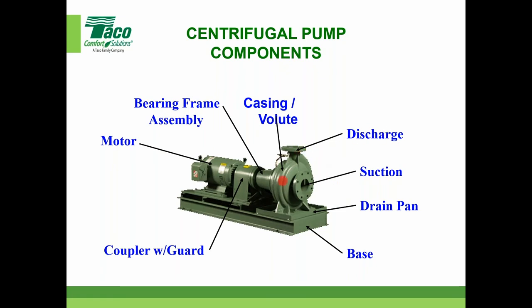Discharge, I think that makes sense. Casing, volute, wet end, they're all synonymous. Bearing frame, we're going to talk about that in even greater detail. Motor, and then a coupler with guard. If you get a chance to download the manuals, I was taking a gander at them this morning, and one of the things it says is, do not operate this piece of equipment without the guard in place. So if you go into a mechanical room and there's no guard around there and you see that coupler spinning, you might want to suggest to somebody privately or more than privately that they put the guard back on, because something bad could happen down the way.